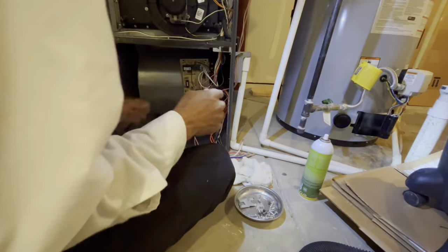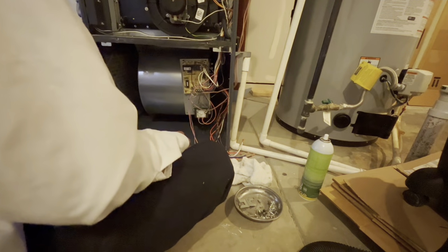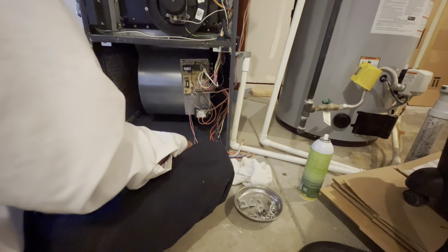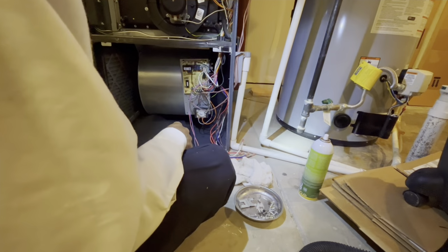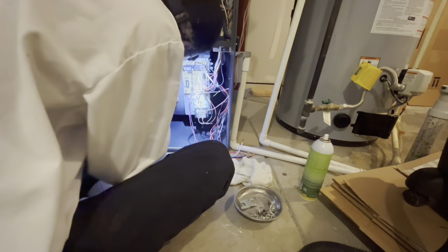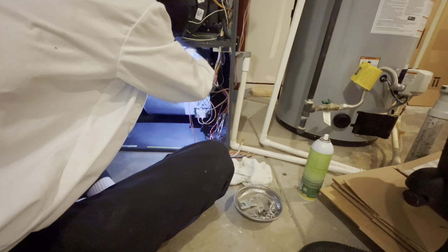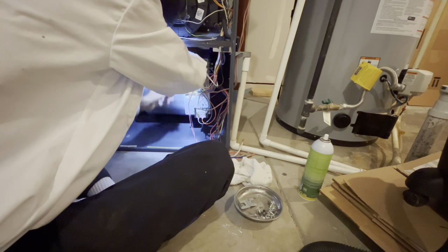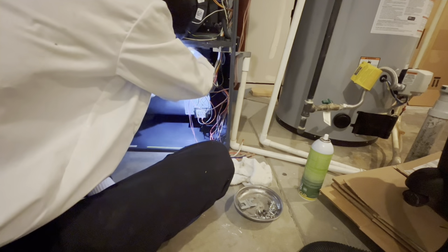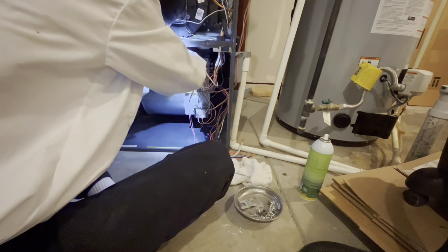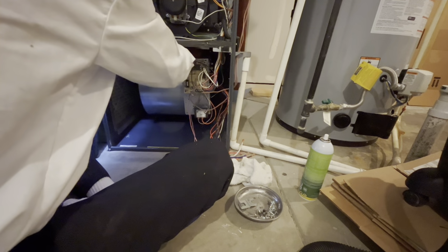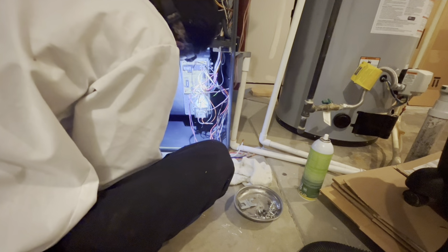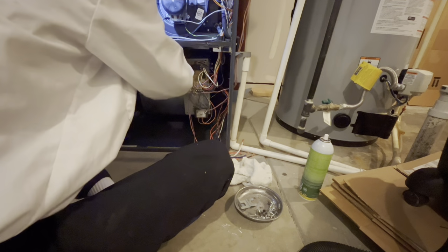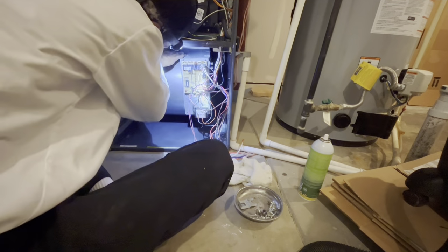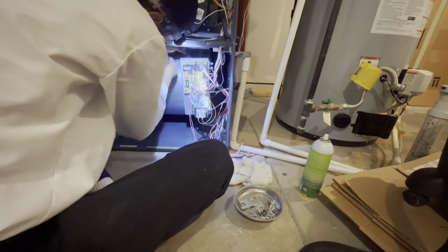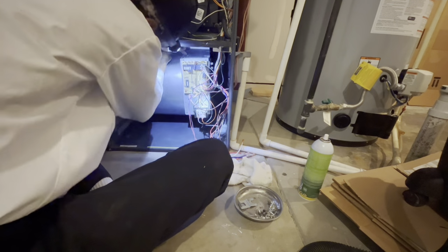So right now I'm sliding everything back in, and there's two screws that go to the top of that bracket that mount into the furnace. And I want to make sure that when you're sliding in that you hit the side brackets. Sometimes it's a full bracket that may be 12 to 18 inches long. Sometimes that bracket may be in 3 different pieces, and if you go under one piece, then that housing and motor will not be installed properly. Then it will make noise. So just take your time.